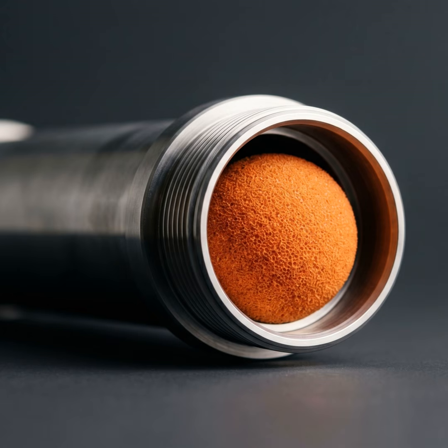I mean, that sounds bad. It is. Yeah. Over time, hour by hour, month by month, they build up. Right. And they don't just build up as a soft, easily washable sludge. They crystallize. They turn into rock. Yeah, they bake onto the metal, forming a hard, calcified mineral scale, and it's often accompanied by biological fouling. Biofilm. Basically slime. Right, which acts like a glue holding the rock to the metal. And this calcified rock is what the sources refer to as the insulation trap. Exactly. Because if copper is a phenomenal conductor of heat, mineral rock is the exact opposite. It's a terrible conductor. Right. It's a phenomenal thermal insulator.